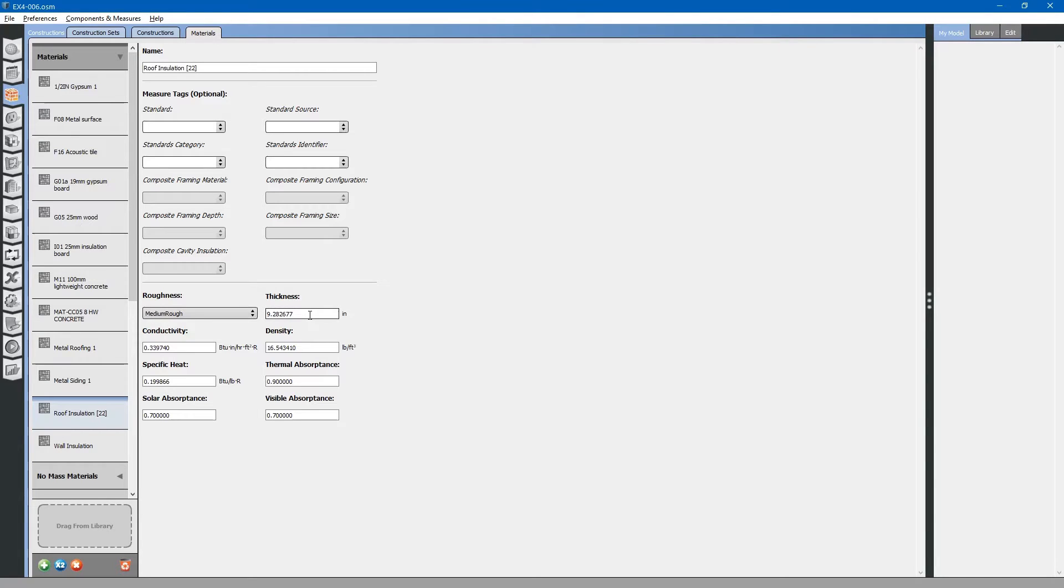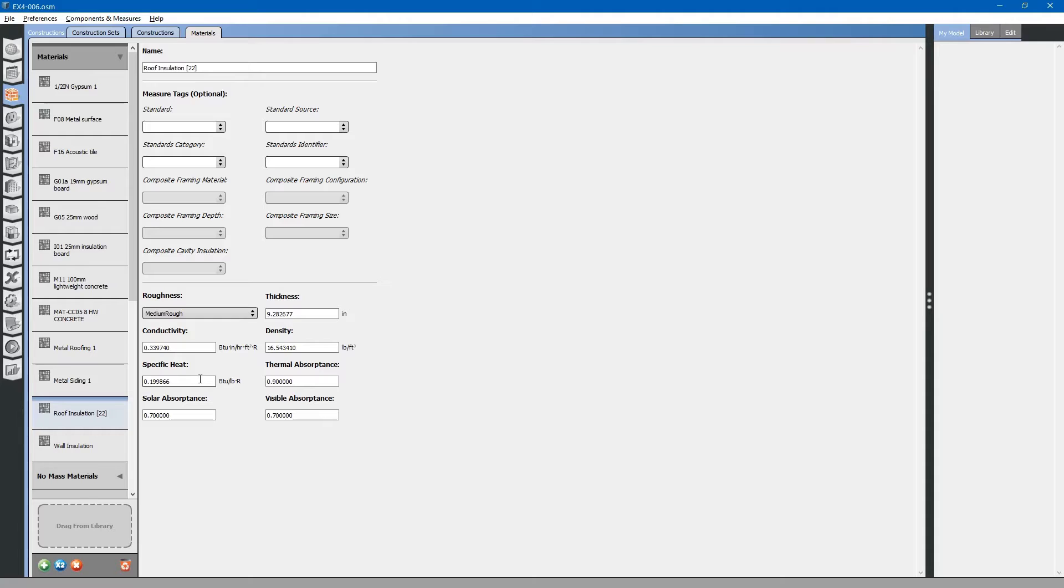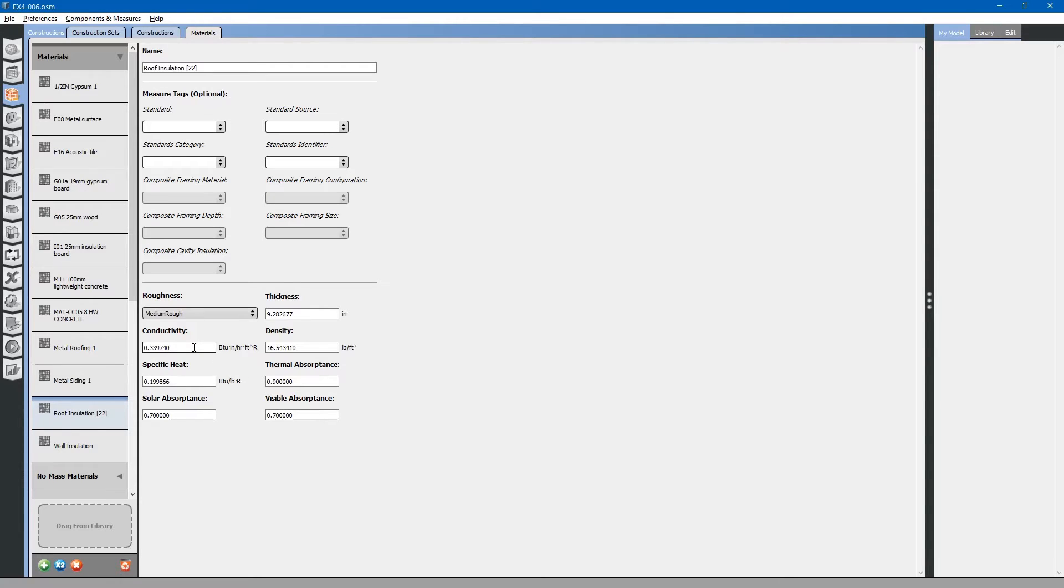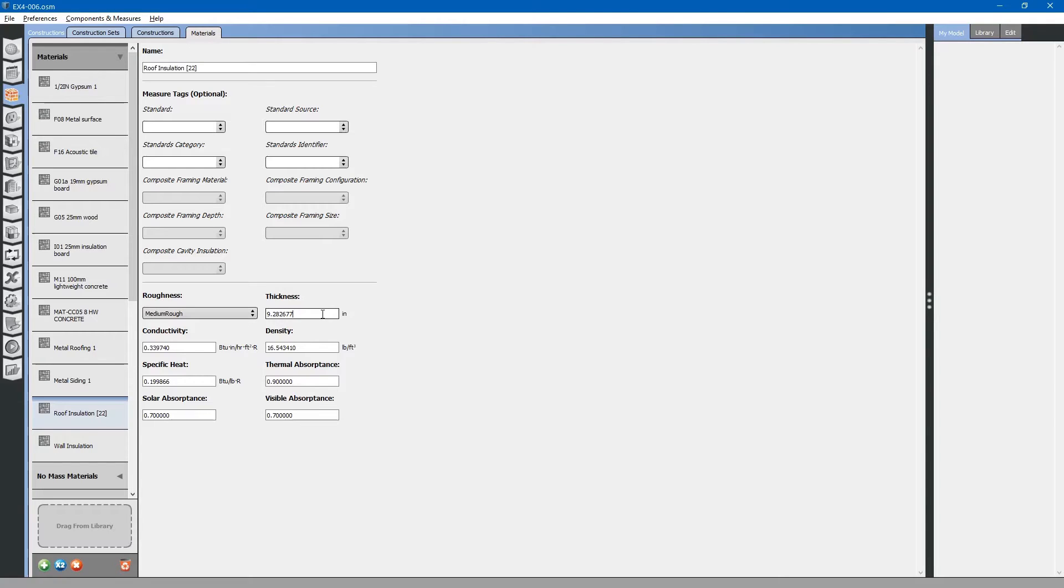You can see that this roof insulation material also has measure tags and it has thermal properties: roughness, how thick it is, thermal conductivity, density, specific heat, and thermal, solar, and visible absorptance. You can see that the thermal conductivity and thickness combined together for this particular roof insulation is approximately an R27 insulative value.